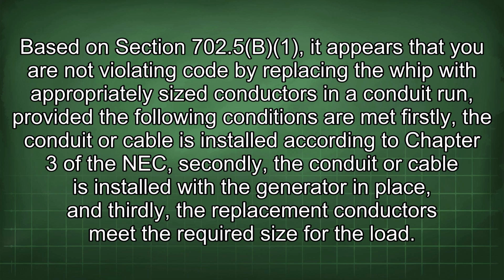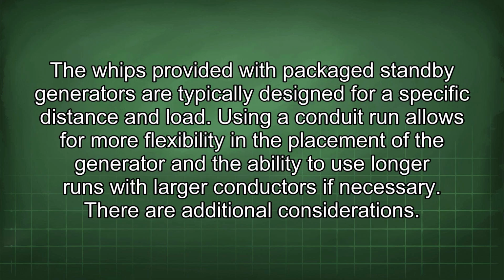Firstly, the conduit or cable is installed according to Chapter 3 of the NEC. Secondly, the conduit or cable is installed with the generator in place. And thirdly, the replacement conductors meet the required size for the load. The whips provided with packaged standby generators are typically designed for a specific distance and load. Using a conduit run allows for more flexibility in the placement of the generator and the ability to use longer runs with larger conductors if necessary.